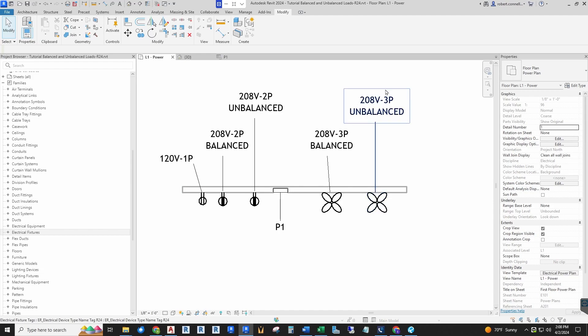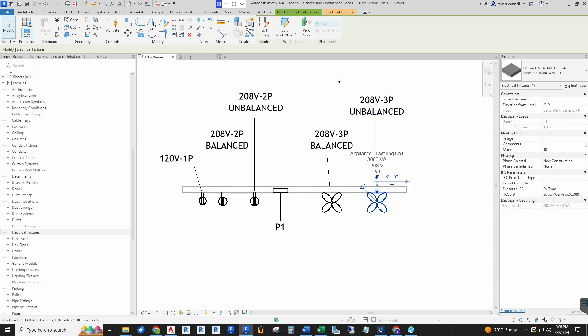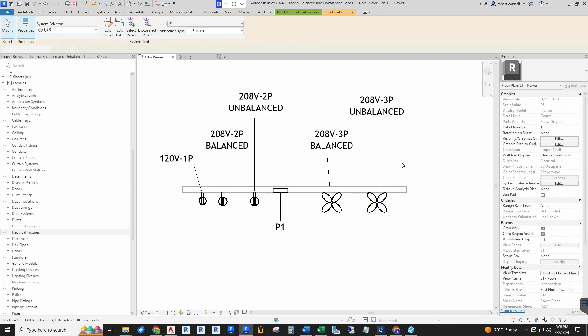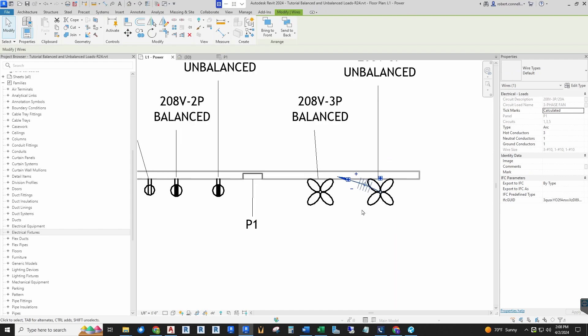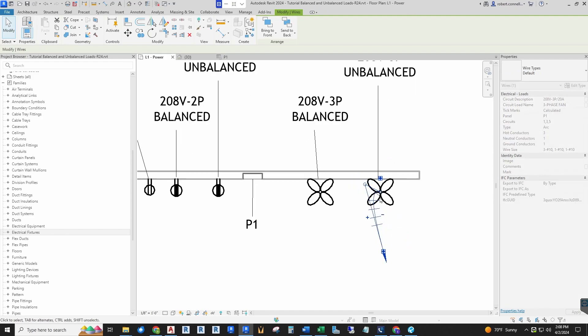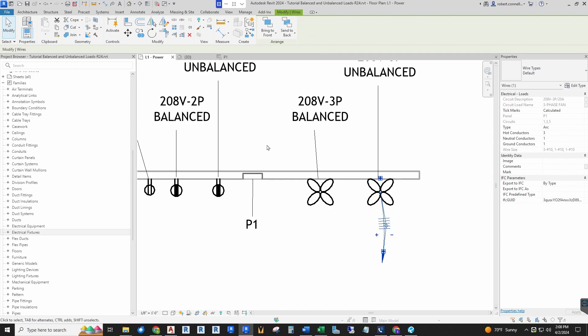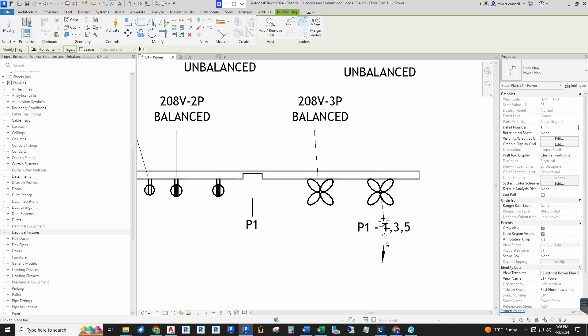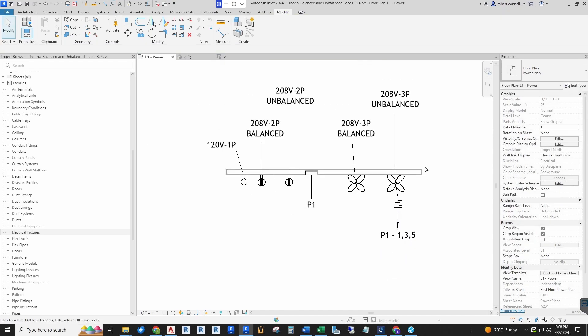The first one I've already connected—this unbalanced 208 three-pole load. It's already connected to panel P1 onto circuits 1, 3, and 5. If I hover over it with tab, I can create an arc wire. Let's go ahead and do this for clarity—get an arc down here so we can see what we have, and let me tag it. I've set up tags for circuits and panels, and I'm using the built-in out-of-the-box Revit devices and fixtures.